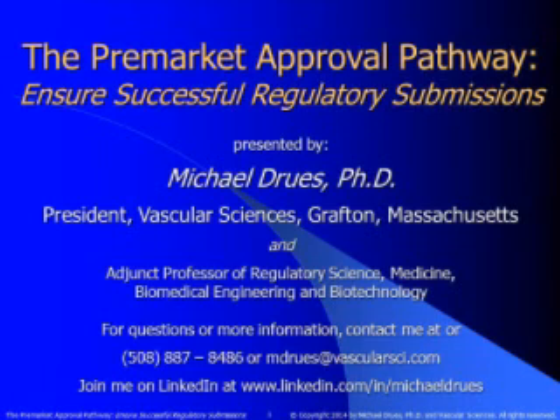A lot of people have confusion as to when you need or don't need an investigational device exemption, or IDE. So let's start out with a general rule, and that is most 510K medical devices do not require clinical data, but some do. On the flip side, most PMA devices do require clinical data, but some do not. So let me say that one more time. Most 510K devices do not require clinical data, but some do, whereas most PMA devices do require clinical data, but some do not. If you understand that, then you'll understand when we need to file an IDE, because an IDE is necessary whenever we're going to be collecting clinical data, human clinical experimentation or clinical trial.